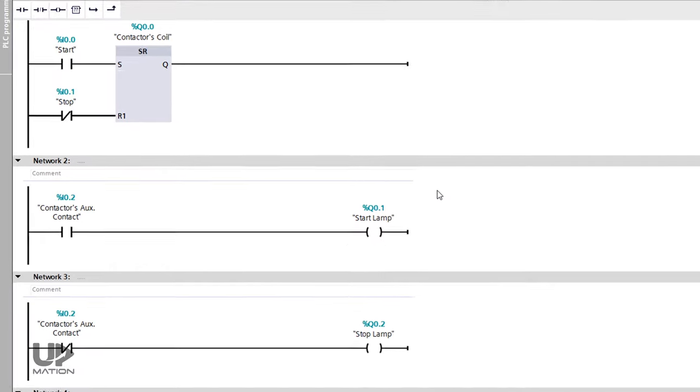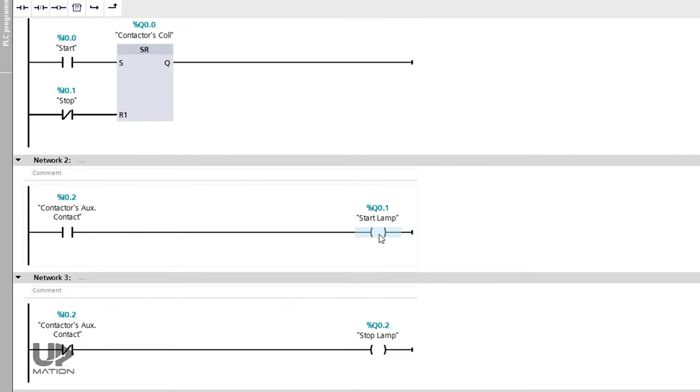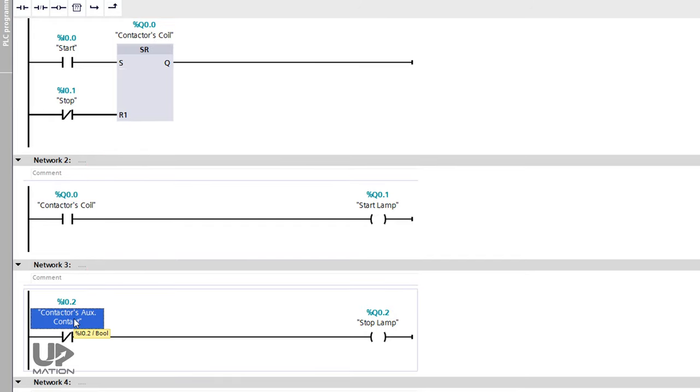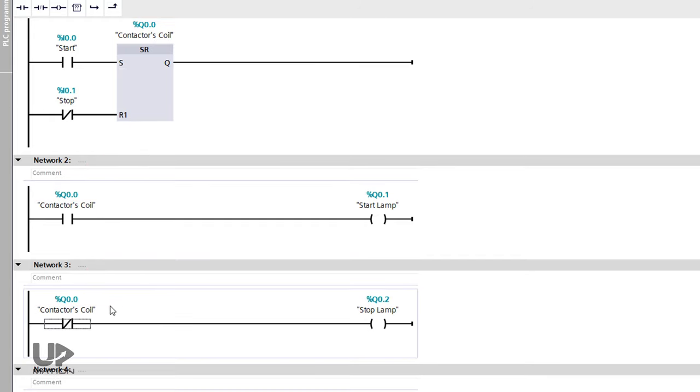For activating and deactivating the lamps, we could also use the contactor's coil output Q0.0. But, as you may have guessed, it's not according to the actual situation in the plant where we have to check the functionality of the contactor in our PLC program, to see if the electricity is really flowing toward the electric motor via the contactor or not.